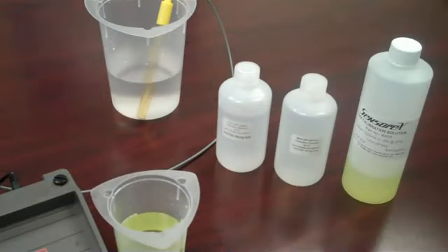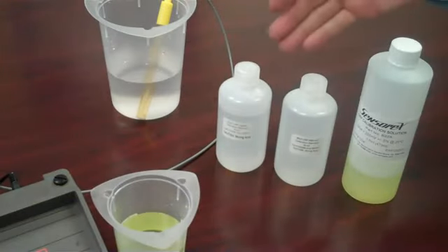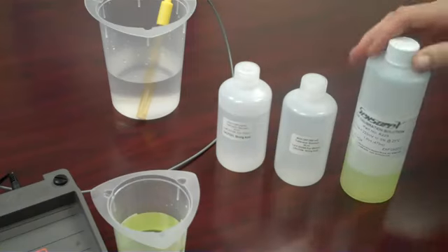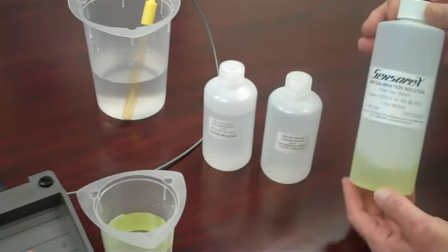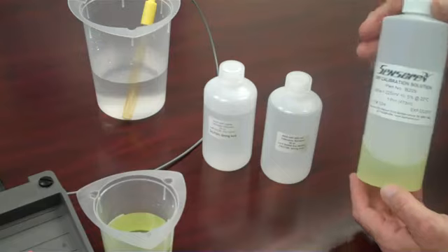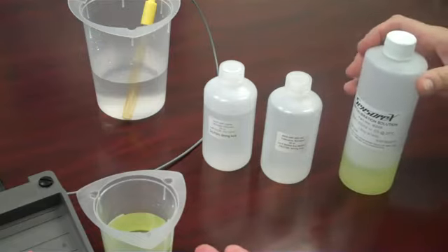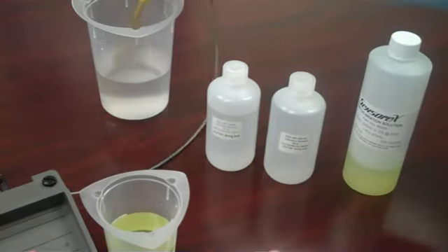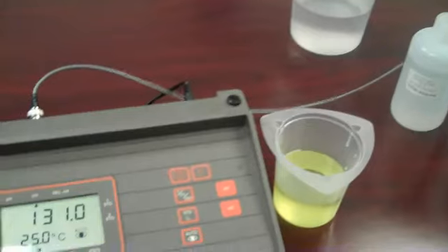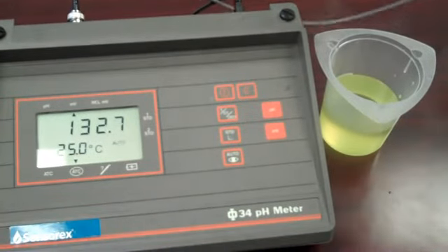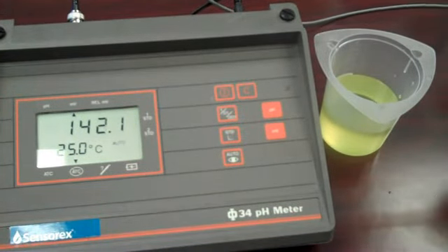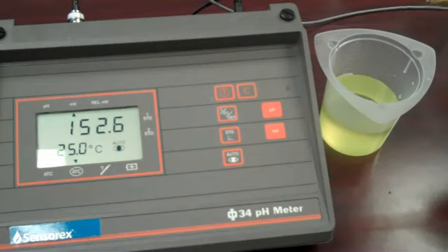Sensorex provides several premixed aqueous solutions with fixed millivolt output. Most popular is known as Zobell solution with an ORP reading of 230 millivolts. I've placed a sample of Zobell solution into a small container. I've connected my ORP sensor to my ORP meter. You might connect yours to your transmitter or controller if you're using that instrument.